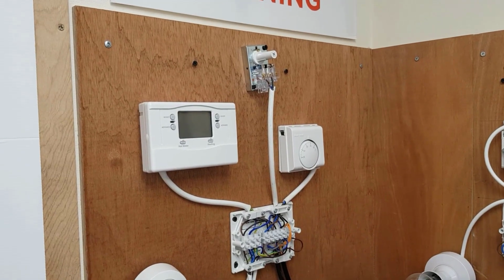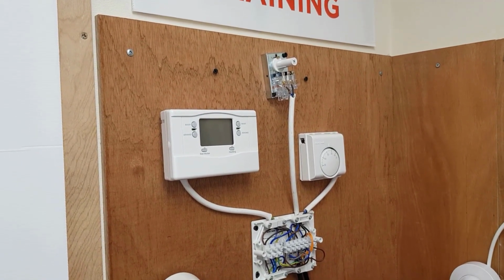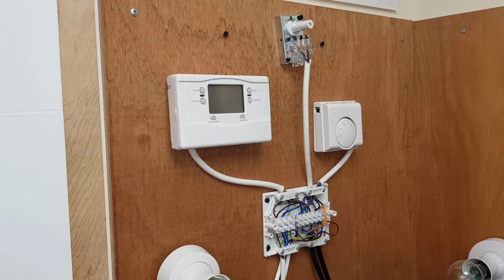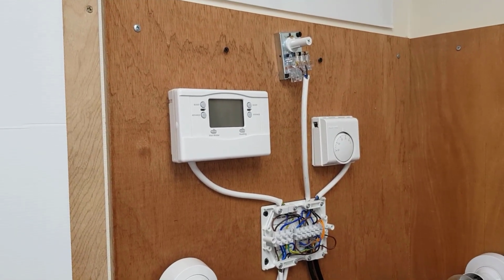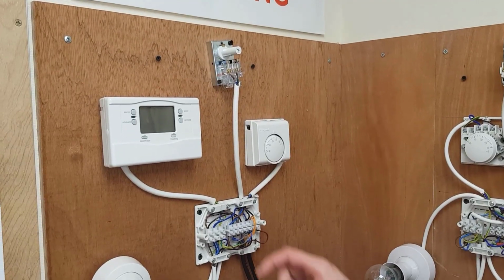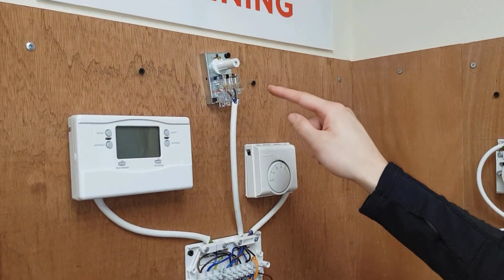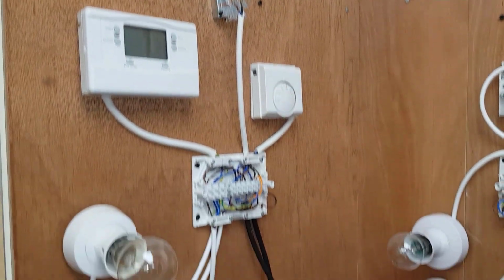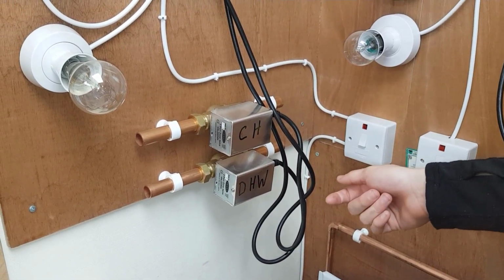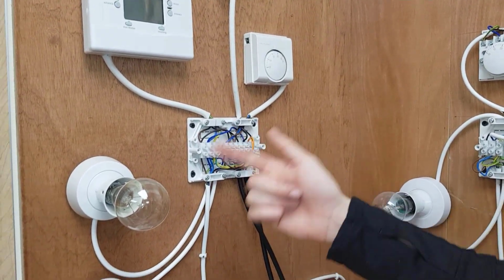So now we're going to move on to the hot water side, but I just want to say on the combi system you can't time the hot water because the sequence is started by opening the hot water tap. So because we have an external hot water cylinder, this is why we need the programmer so that we can control the hot water side. So for this hot water side we need a demand on our programmer, which then sends power to our cylinder thermostat, which makes a switch coming down to our hot water zone valve, which then turns the motor inside, making a micro switch which comes up to these orange wires, which then activate the pump and the boiler.